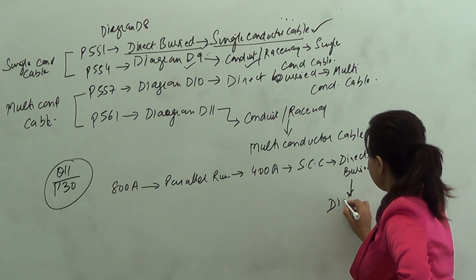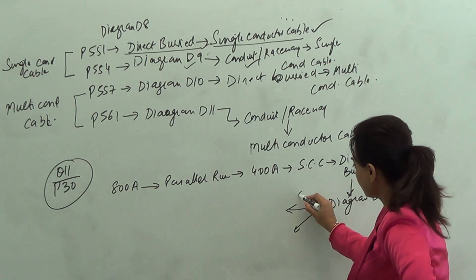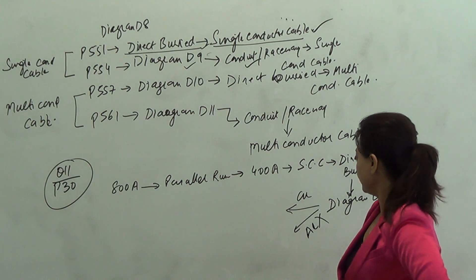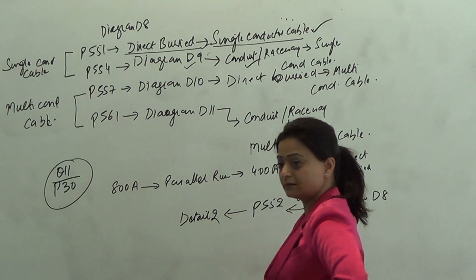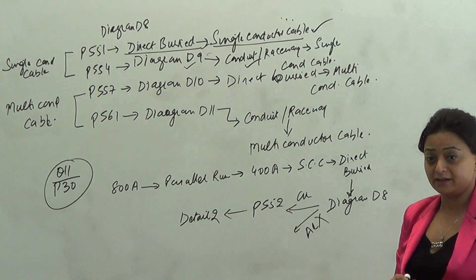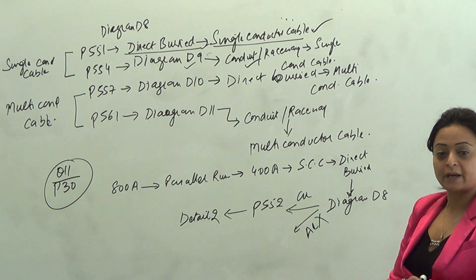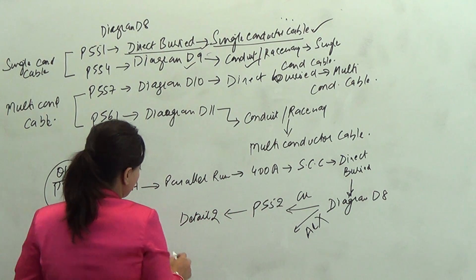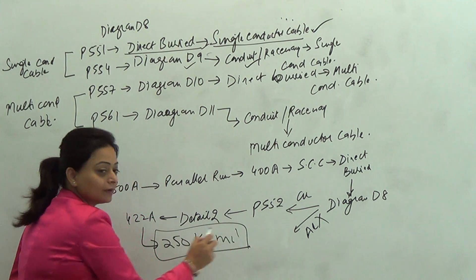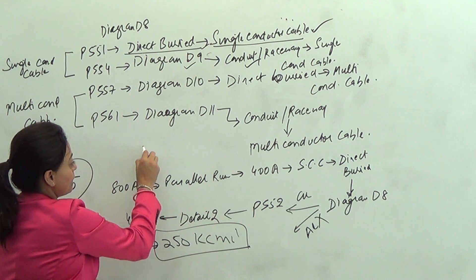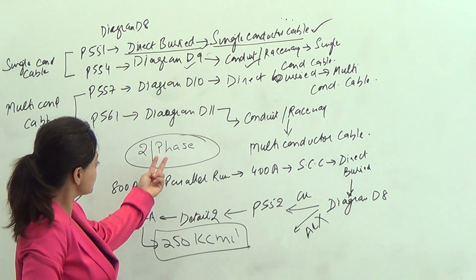D8 refers to two tables — one is copper, one is aluminum. Because the conductors are not aluminum, we go to page 552. Look for detail 2 because detail 2 is the parallel run column. Detail 1 is one cable per phase but detail 2 is two cables per phase. On detail 2, you are looking at 400 amps — what's your closest match? 422 amps, which refers to 250 kcmil. That's your answer. When your book says two per phase, it doesn't mean two-phase — it means two cables per phase, which means parallel run.